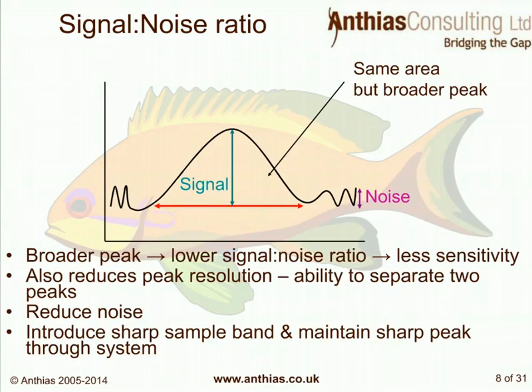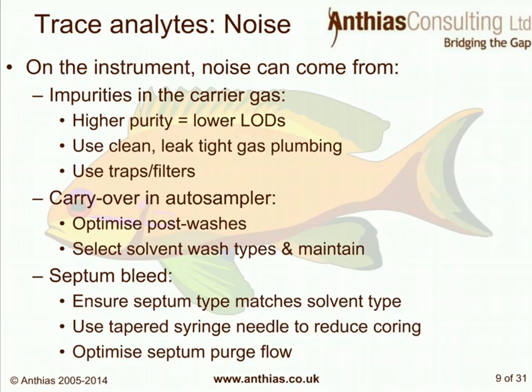Noise can come from impurities in the carrier gas — the higher the purity, usually the lower the limits of detection. We also need very clean, leak-tight gas plumbing and should install traps or filters to remove moisture, oxygen, and hydrocarbons from the gas supply. Carryover from the autosampler is another noise source — optimize the number of post-washes to ensure the syringe is completely clean, and select a suitable solvent wash that removes both analytes and the higher-loading matrix peaks.